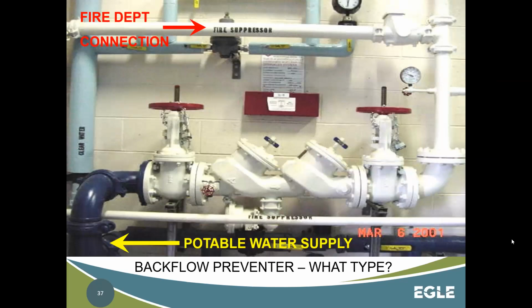The easiest and quickest way to tell apart if something is a double check valve or an RPZ is going to be the little additional port or vent that comes with the RPZ, where it can discharge in the event that backflow occurs. Again, a double check valve would not have this relief port on the bottom.